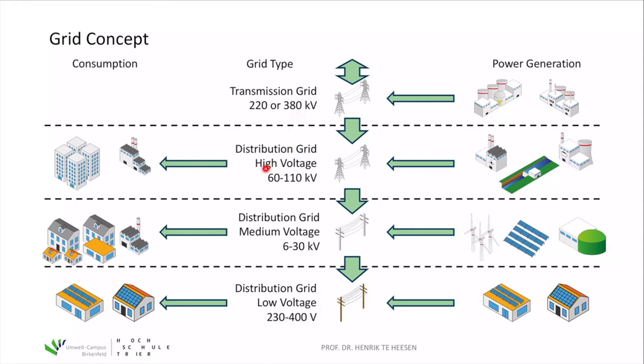The second level is the high voltage grid with a voltage of 60 to 110 kilovolts, which is a distribution grid level. Power generation comes from mid-sized coal power plants in the hundreds of megawatts capacity, big gas power plants, or large hydropower plants feeding energy directly to this voltage level. On the consumption side, very big cities take electricity from this grid level, as do big industries like the steel industry, which need a lot of energy.